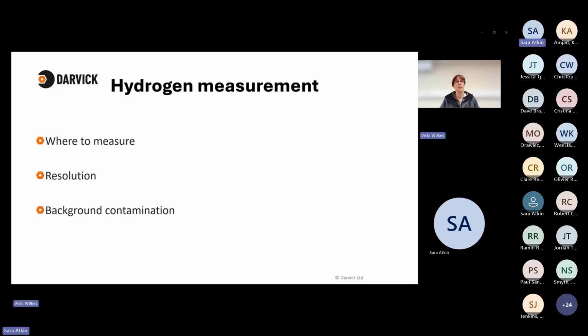And then you've got the question, if you're trying to measure the permeation of hydrogen, so from the inside of a sample to the outside, in a vacuum, that is much more complicated, because you've got very, very low levels of hydrogen. So you've got to make sure that you've got enough resolution on your measurement equipment to ensure that you're picking up actual hydrogen coming through the sample. And where do you put that? Because where does that hydrogen travel in a vacuum? How is it going to move from the sample surface to your measurement sensor? You can't fill your entire chamber with sensors.